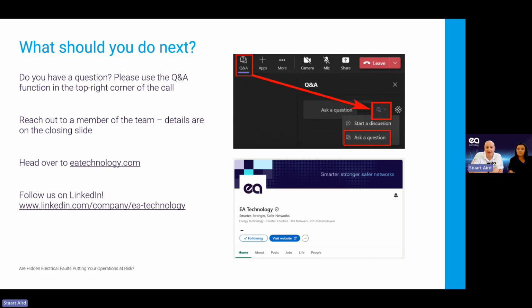Hi, is an annual PD survey recommended on 11 kV switchgear, which we normally see in the UK? What areas, and what tech would be best suited? So yes, 11 kV switchgear is a very, very common PD survey that we do. We do PD surveys of that type of asset weekly in a lot of industrial sites, and I know a lot of distribution companies in the UK do a lot of PD on that level as well. So 11 kV is definitely one to do.